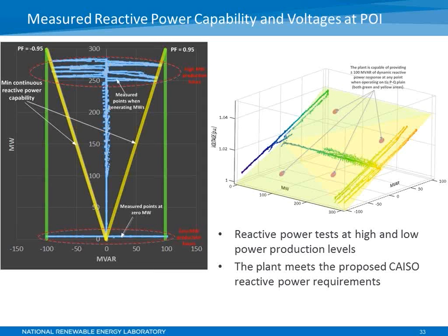So all blue data points there are the actual measured reactive power of a plant at different active power levels. You see that this data demonstrates that the plant meets the expected reactive power capability, which is shown by this yellow triangle. In addition, the plant is capable of producing and absorbing reactive power at close to zero power production.